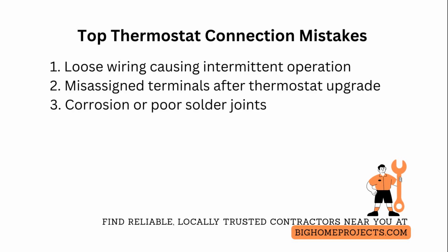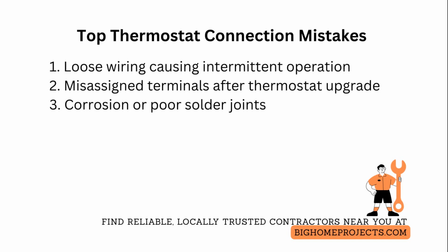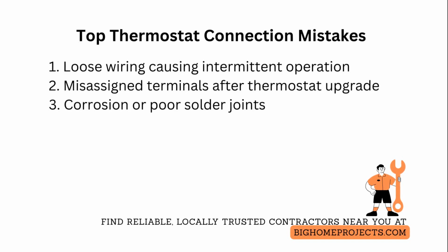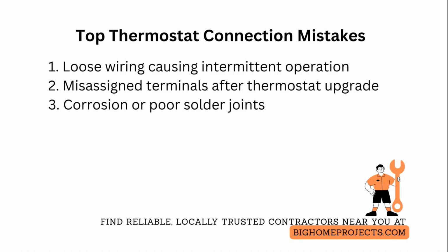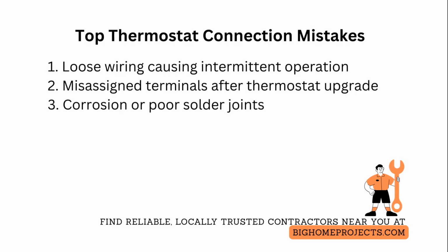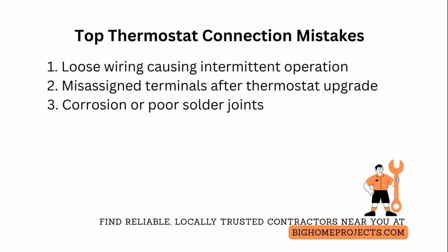One of the third mistakes is leaving corrosion or poor solder joints unaddressed that later cause failures. Search keywords such as control board corrosion repair and solder joint inspection. And the solution is careful cleaning, reflowing suspect joints with a temperature-controlled soldering iron, and, when in doubt, replacing the control board.